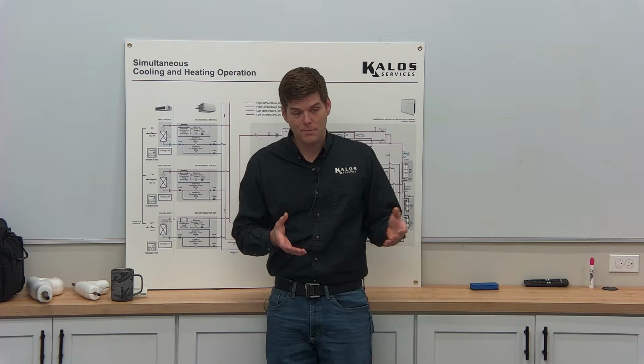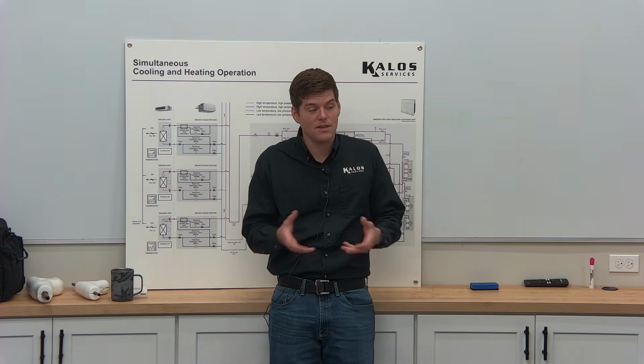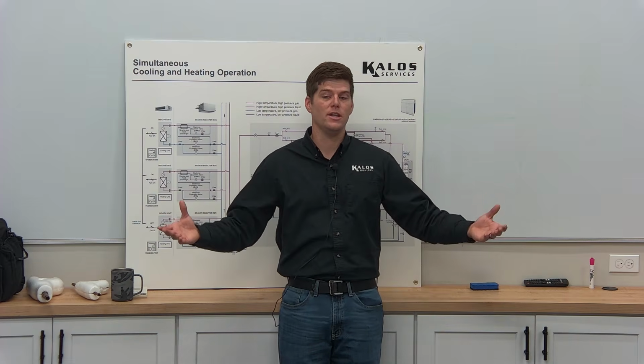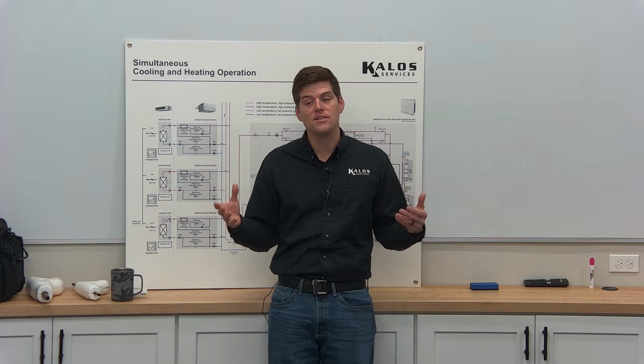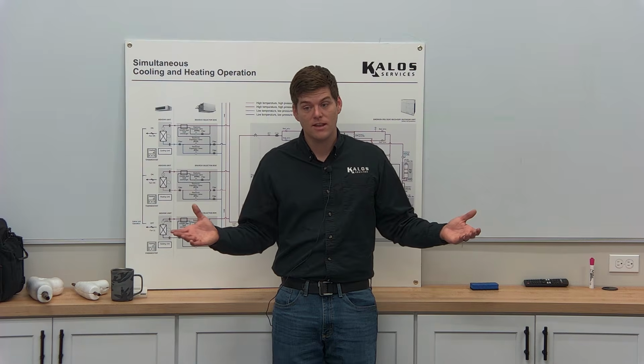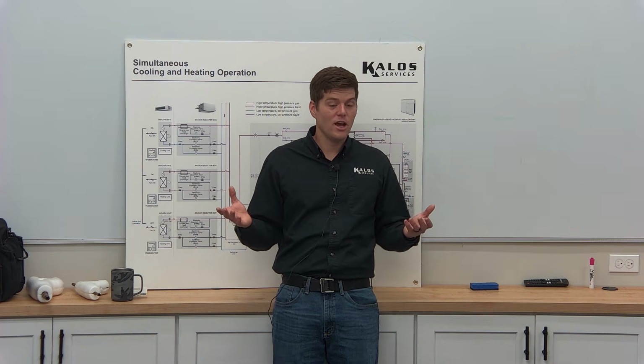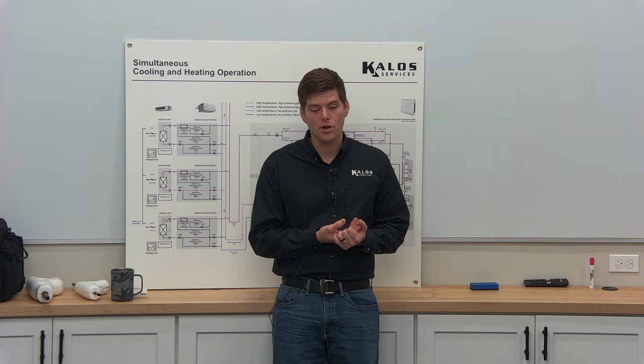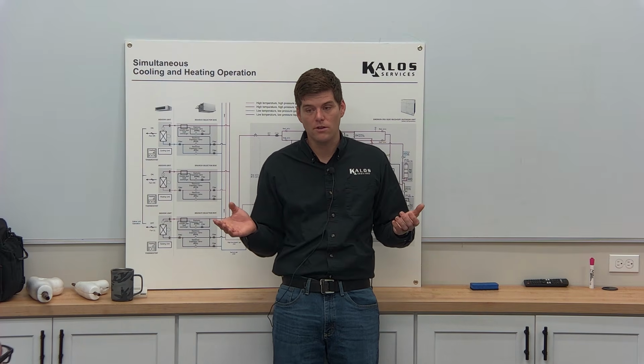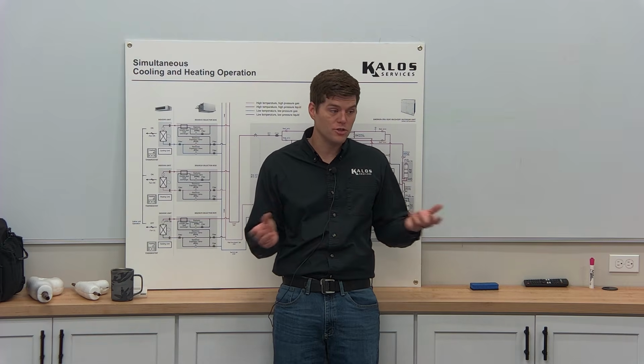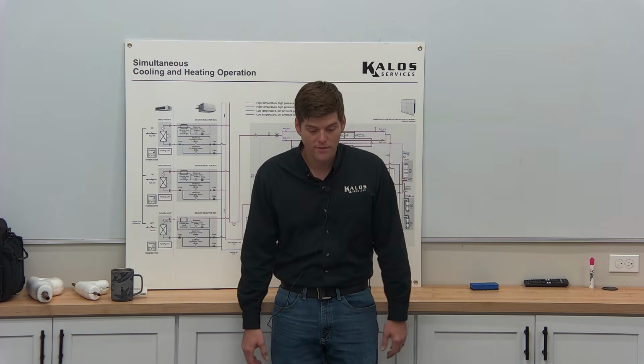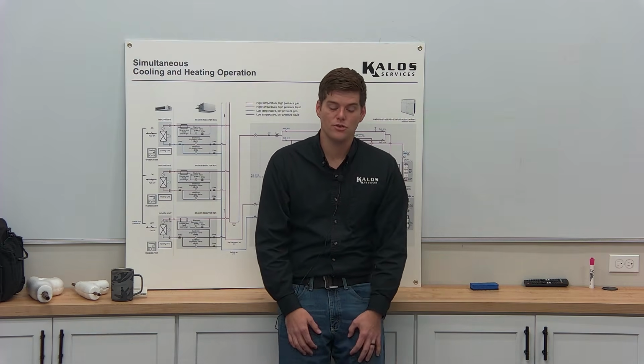This system, depending upon the size of the outdoor unit, has up to 168 different speeds. All right, that's a lot of speeds. A lot of you guys may have been exposed to Copeland's digital compressor out in the wild, in AAON units, some of the larger split systems. We have a couple clients and customers that have digital compressors.